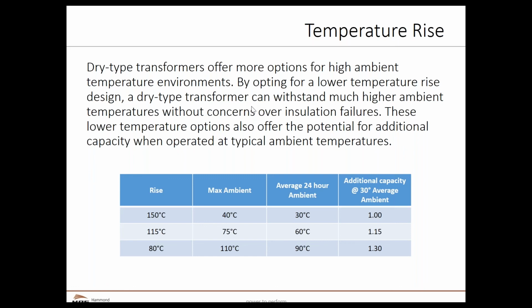When we look at the additional capacity, you can see that that's at a 30°C average ambient versus the column just to the left of that, which has higher average ambience. So again, a lot of additional temperature rise options with dry type that can affect the design protocols and the equivalent kVA that you would be specifying and using.